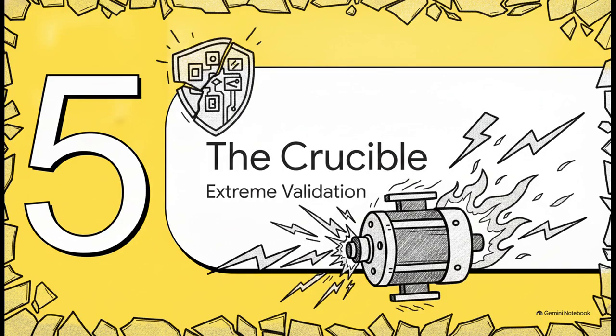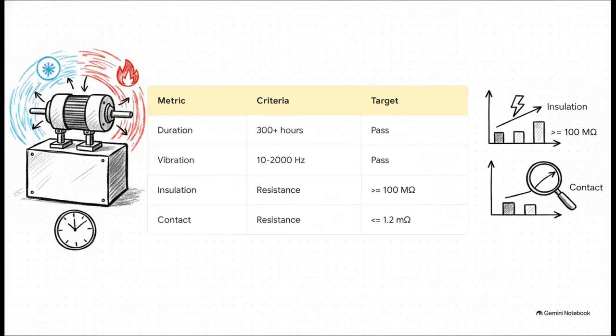Finally, Section 5, the crucible, our DVP&R extreme validation. Before anything gets approved for mass production, it goes through absolute torture. Engineers simulate the definitive worst-case scenarios. They take the entire motor assembly, mount it onto a massive shaker table, and violently shake it with 3-axis wideband vibrations ranging from 10 to 2,000 hertz. And while they're shaking it, they continuously swing the environmental temperature from -40 degrees freezing to 150 degrees boiling Celsius. They do this non-stop for over 300 hours. To even pass, the insulation resistance has to remain at or above 100 megaohms, and the contact resistance cannot increase by more than a microscopic 1.2 milliohms.